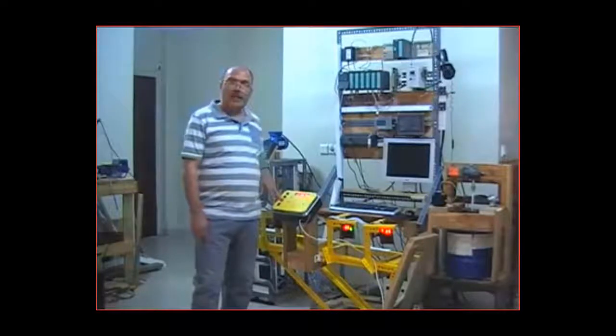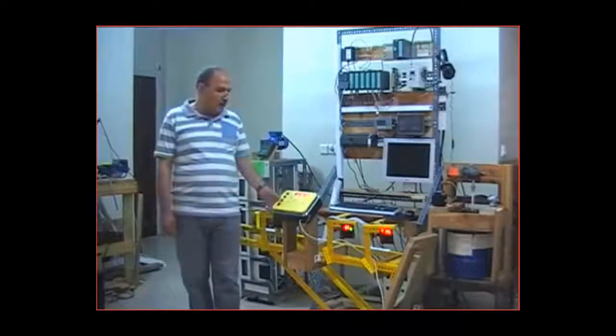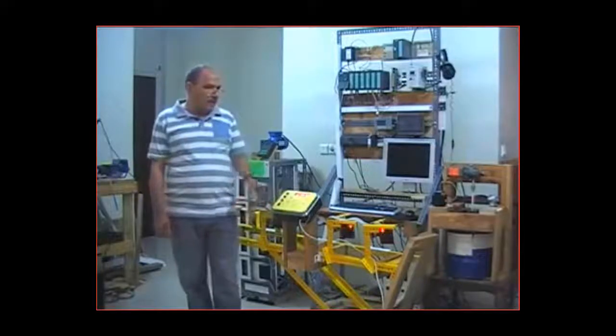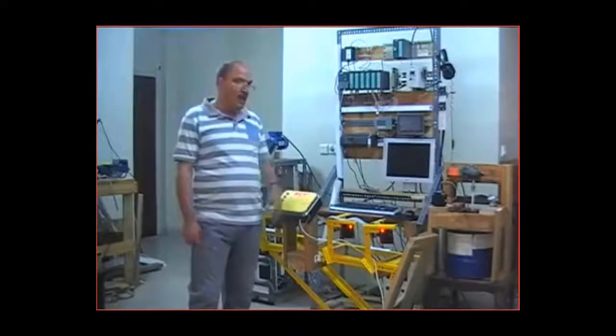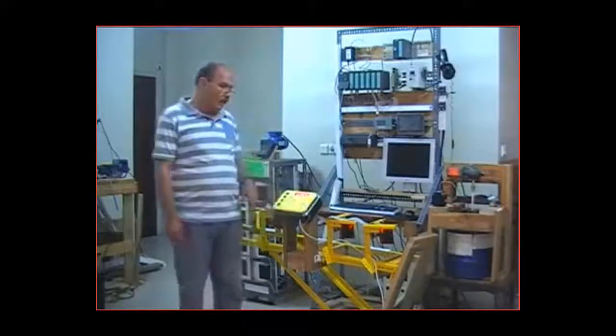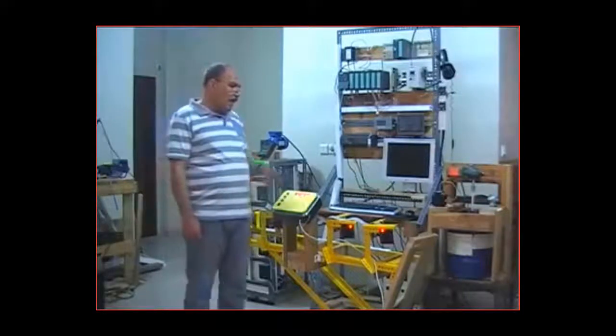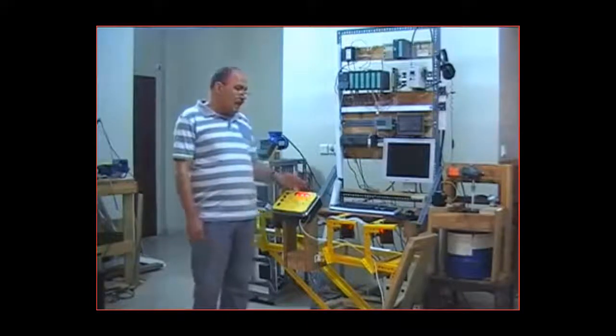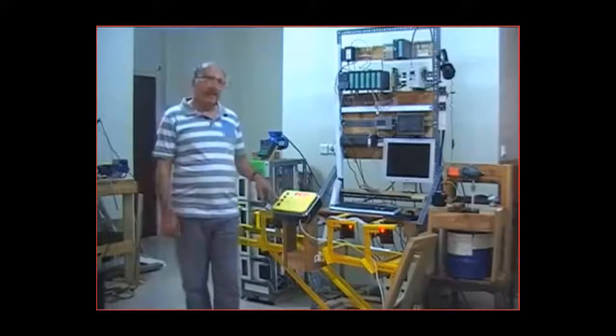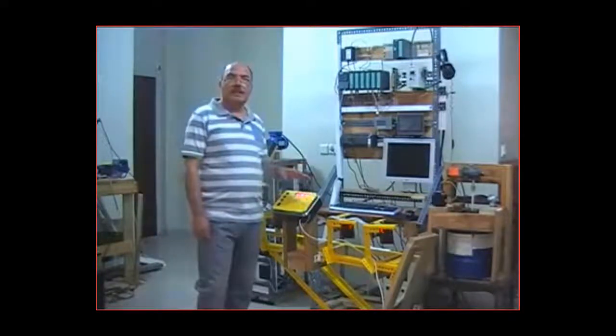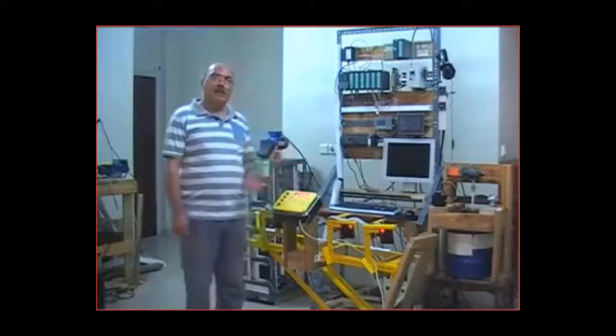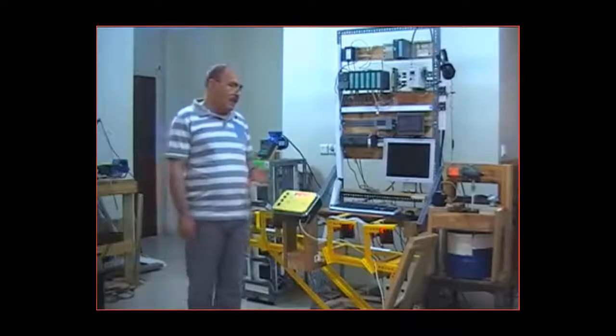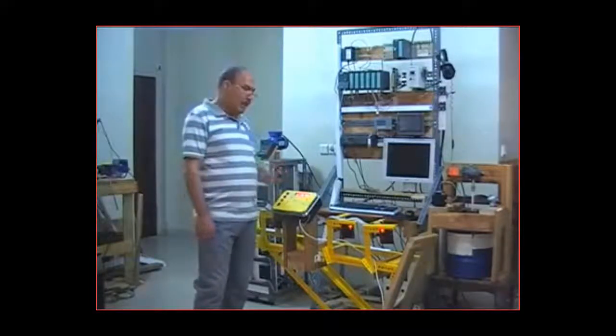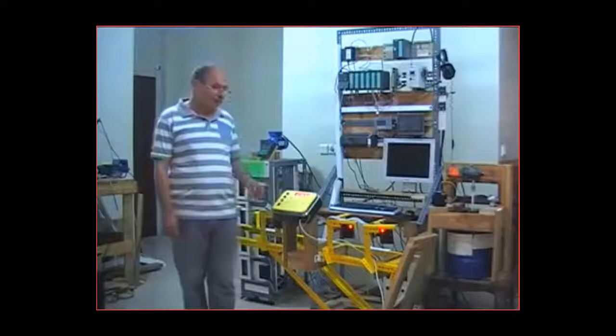Also, a push button is installed on the panel. When it is depressed, the system goes to emergency mode mandatorily. As long as it is not depressed again, the system stays in this mode. When it's depressed again, it comes out of the mode and continues its normal function.